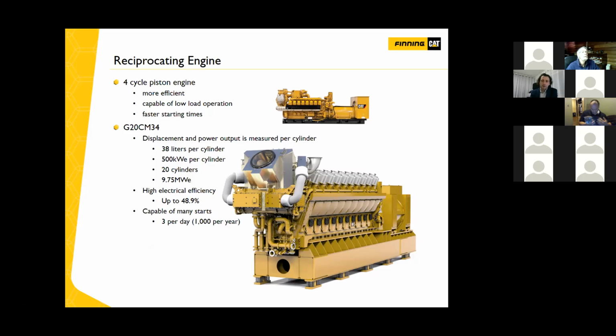Yes, we are capable of low load operation, and we can handle so many hours of it. But after low load operation, we're still going to ask you to do a recovery operation, where we load the genset in steps up to rating to ensure there's no carbon buildup and so on.